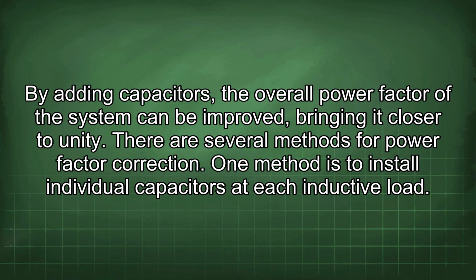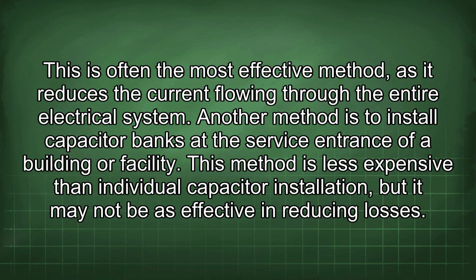There are several methods for power factor correction. One method is to install individual capacitors at each inductive load. This is often the most effective method, as it reduces the current flowing through the entire electrical system. Another method is to install capacitor banks at the service entrance of a building or facility. This method is less expensive than individual capacitor installation, but it may not be as effective in reducing losses.